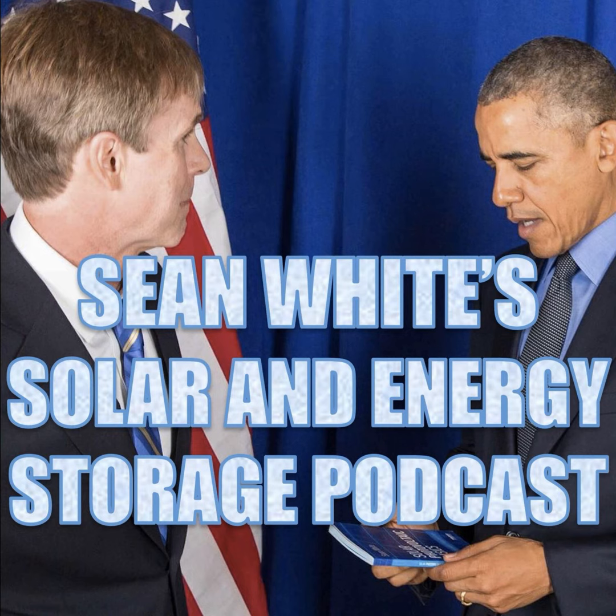The Sunny Boy storage actually has a secure power supply, just like the SMA Sunny Boy inverters do these days. That means you basically have one outlet you can plug into, so you don't have to do all this extra special wiring and install a separate sub panel. If that's enough for somebody—just one outlet, or about 2,000 watts—that Sunny Boy storage will back up 2,000 watts without having to get fancy.